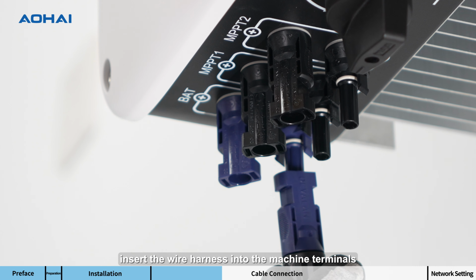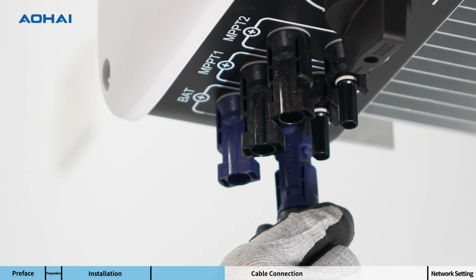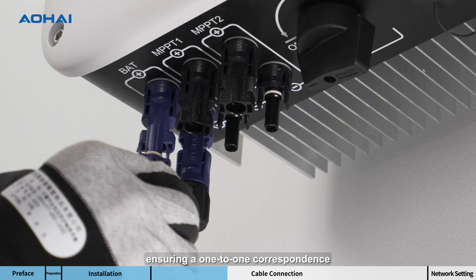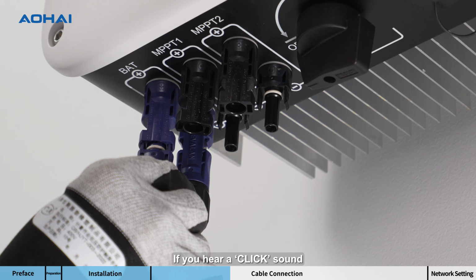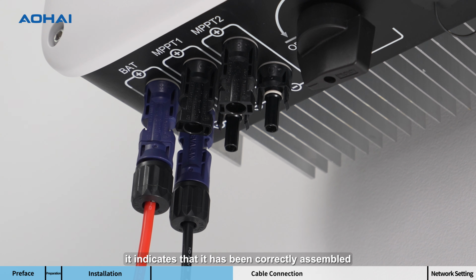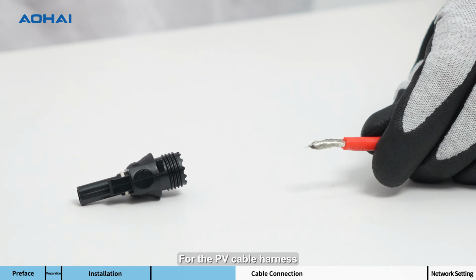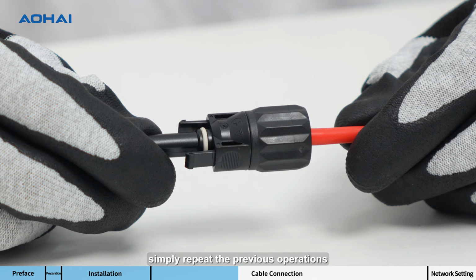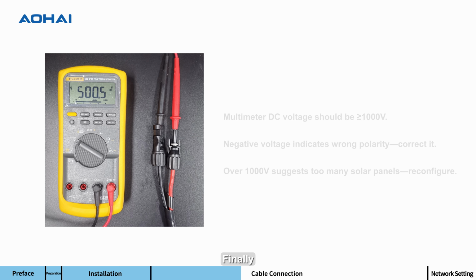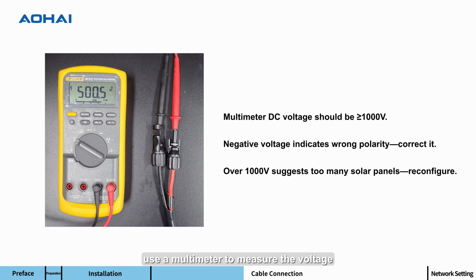Then, insert the wire harness into the machine terminals, ensuring a 1-to-1 correspondence. If you hear a click sound, it indicates that it has been correctly assembled. For the PV cable harness, simply repeat the previous operations. Finally, use a multimeter to measure the voltage, ensuring the polarity is correct.